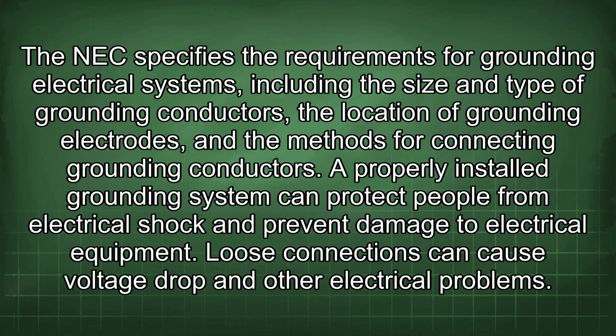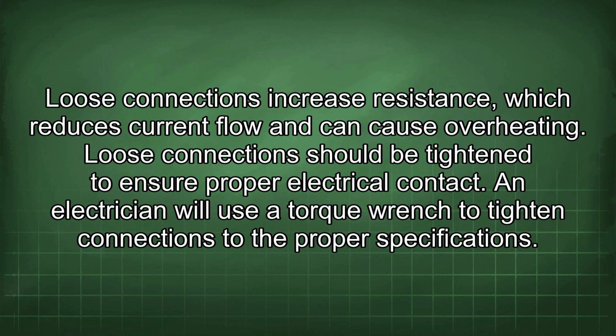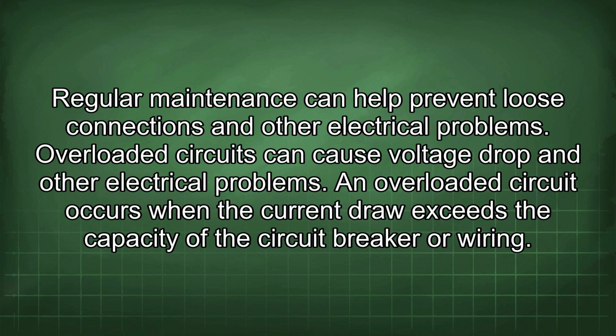Loose connections can cause voltage drop and other electrical problems. Loose connections increase resistance, which reduces current flow and can cause overheating. Loose connections should be tightened to ensure proper electrical contact. An electrician will use a torque wrench to tighten connections to the proper specifications. Regular maintenance can help prevent loose connections and other electrical problems.